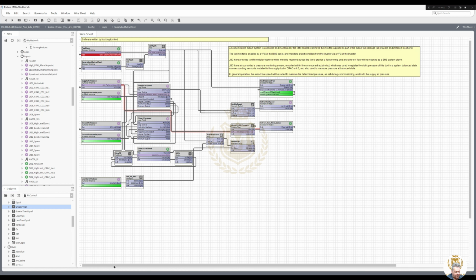Now, do I need... No, I'm not going to put the enable of a CRAC unit there. Or am I? Because we've not enabled any CRAC units yet. I don't think. If I look at my digital outputs folder, yeah, none of them have been enabled yet. So I don't even know when I enable them yet. There's no points here on the intent, so it's not in the logic. There is for that, there is for that. They're all spare.